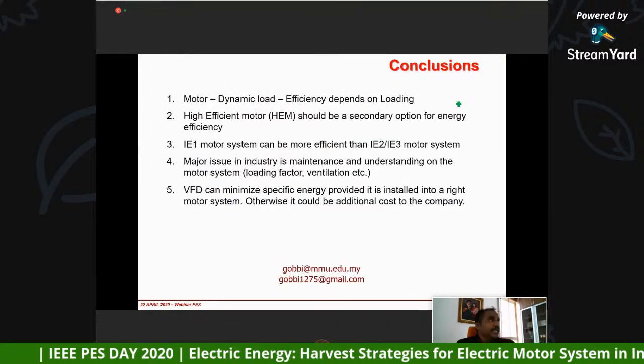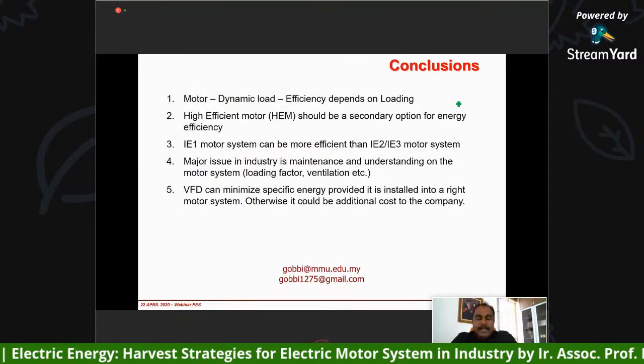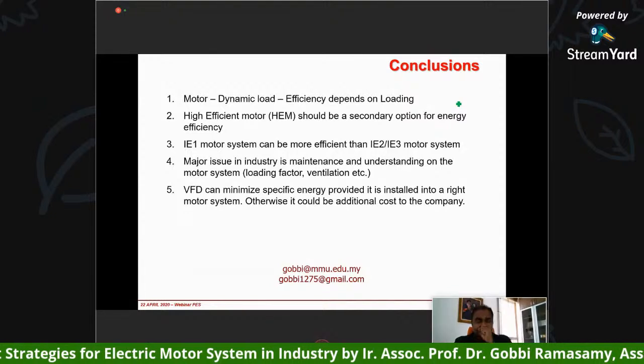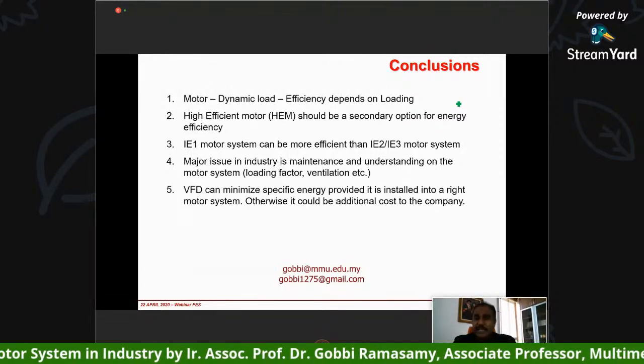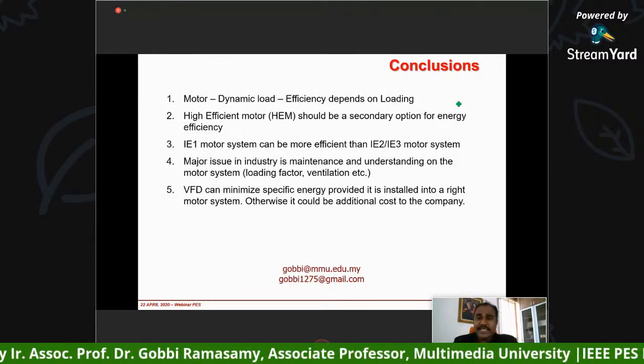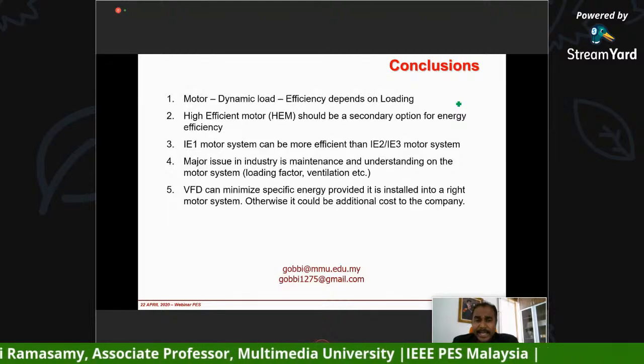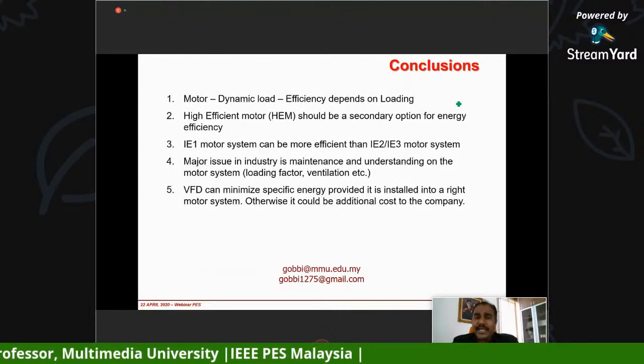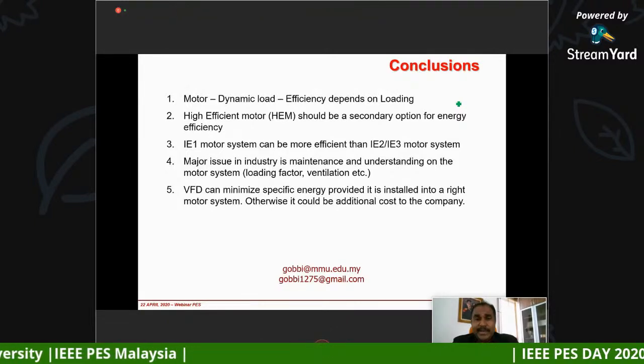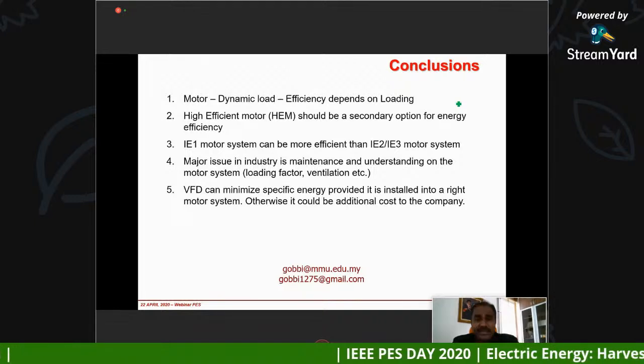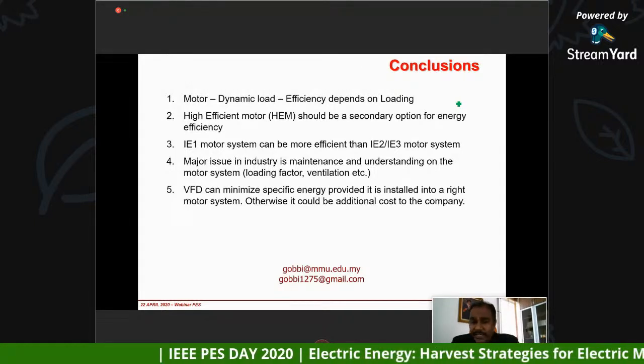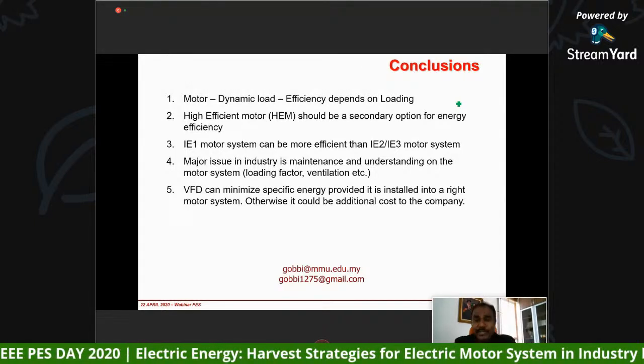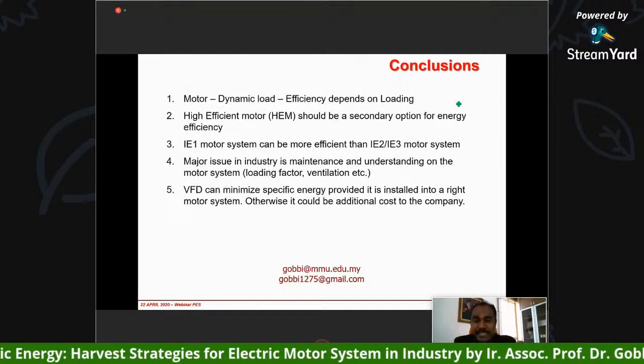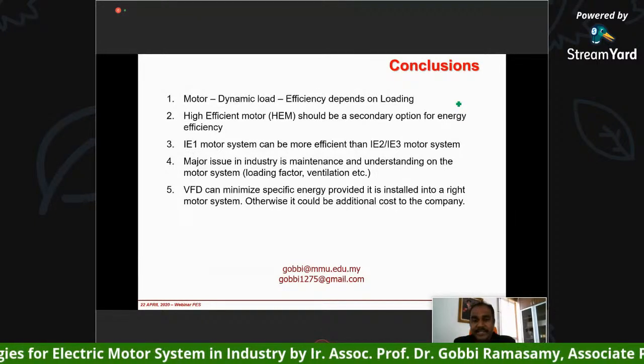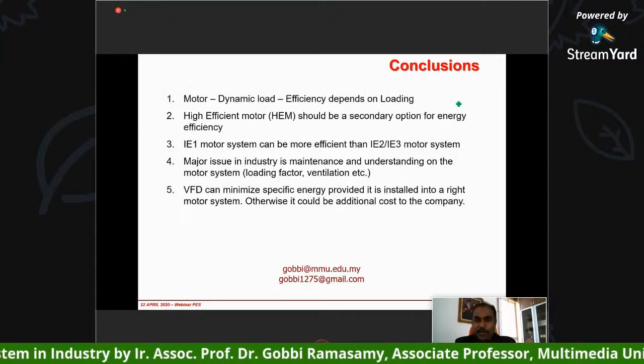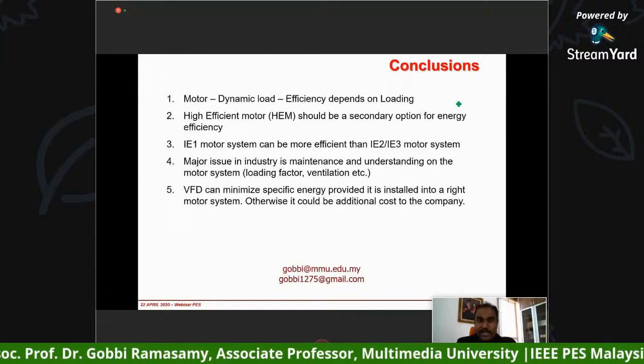As a conclusion, as I mentioned to you, when it comes to motor, it is a dynamic load. You have to understand the efficiency depends on the loading. Therefore, high efficient motor should be a secondary option. Don't blindly change it to high efficient motors because it may not give you any savings. So you have to look at the loading condition first. Make sure that you optimize the current system. Make sure that it runs at 70% or 80% load before you think about going for high efficient motors.